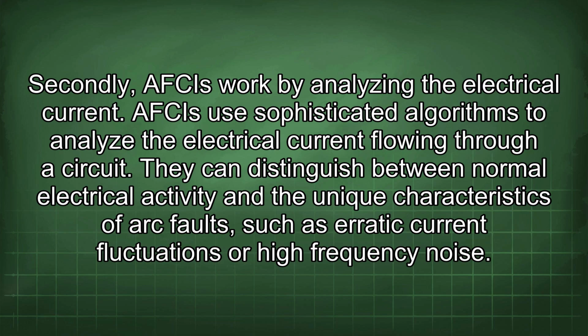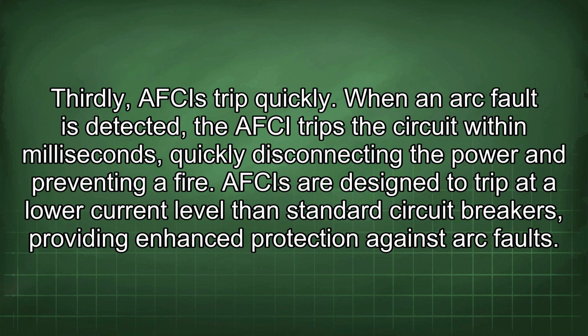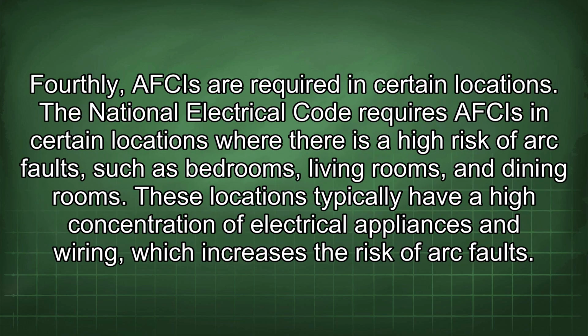Secondly, AFCIs work by analyzing the electrical current. AFCIs use sophisticated algorithms to analyze the electrical current flowing through a circuit. They can distinguish between normal electrical activity and the unique characteristics of arc faults, such as erratic current fluctuations or high-frequency noise. Thirdly, AFCIs trip quickly. When an arc fault is detected, the AFCI trips the circuit within milliseconds, quickly disconnecting the power and preventing a fire. AFCIs are designed to trip at a lower current level than standard circuit breakers, providing enhanced protection against arc faults.